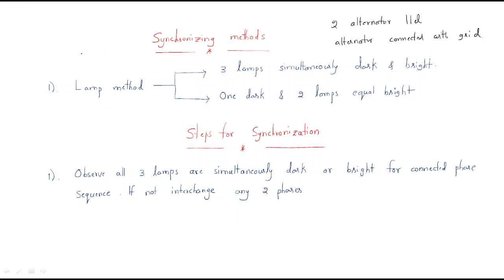Synchronization is done by the lamp method. In the lamp method there are two approaches: first, three lamps are simultaneously dark or bright; second, one lamp is dark and two lamps are equally bright.